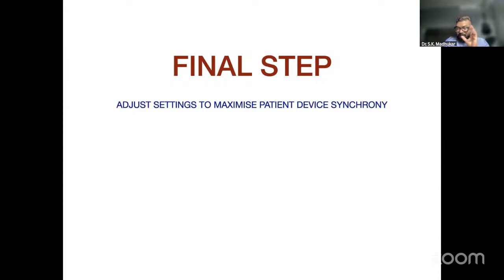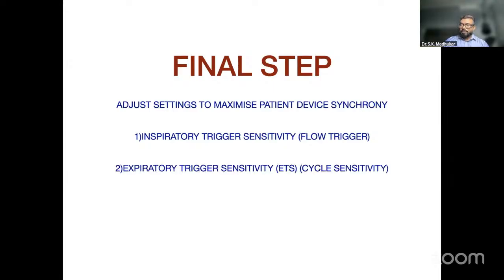To maintain the synchrony, we need to adjust a few things. And those are inspiratory trigger sensitivity, the flow trigger, which I just talked about. Second, expiratory trigger sensitivity, ETS, cycle sensitivity. This is really, really important. Third is inspiratory time and TI max. And last is P ramp or rise time.